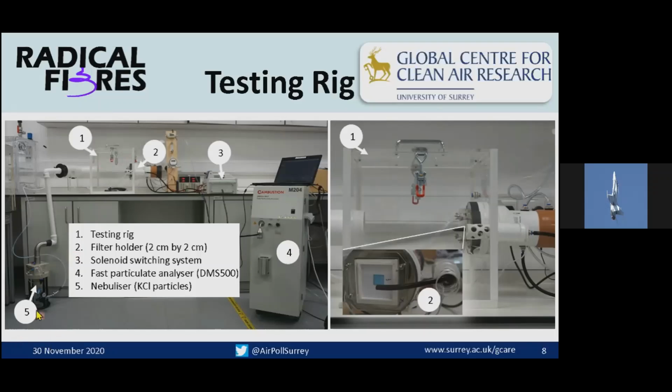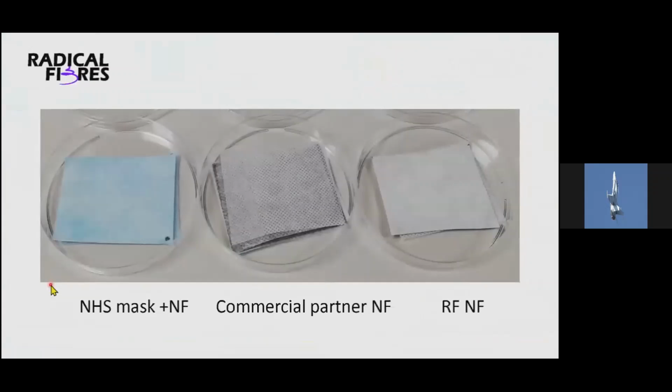They have a nebulizer, a potassium chloride, same as everybody else. And as you've heard before, the particles we test for are from just a little bit above 10 nanometers up to about 300 nanometers, because our challenge was to stop particles below the 100 nanometer level.